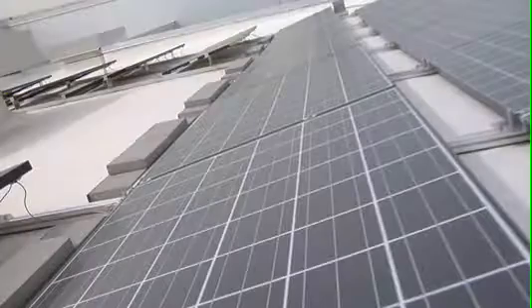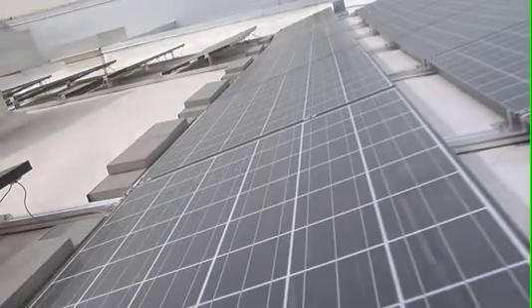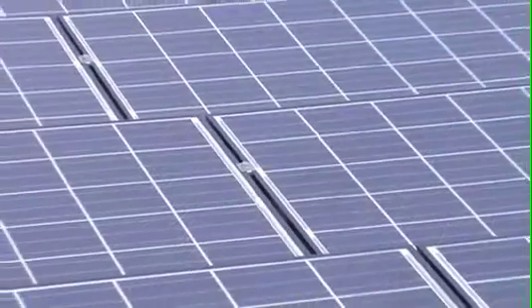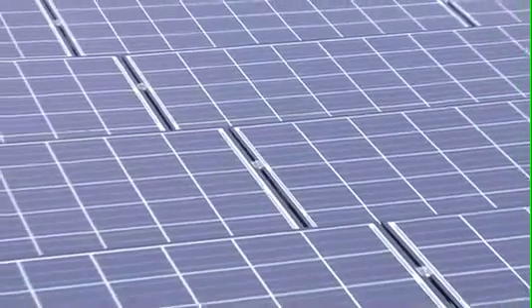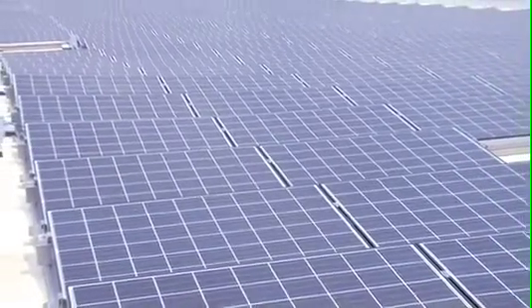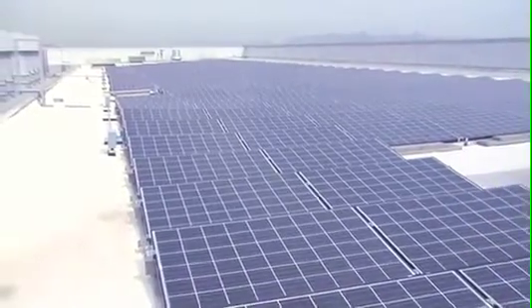The basis of this solar generating system is the panel. There are three types of panels used: monocrystalline, polycrystalline, and amorphous. The polycrystalline, which is what we have here, is the best value for the dollar. Each panel runs at 20 volts, 205 watts. We then hook the panels together in series to come up to 400 volts, which is what we want to feed into the main system.